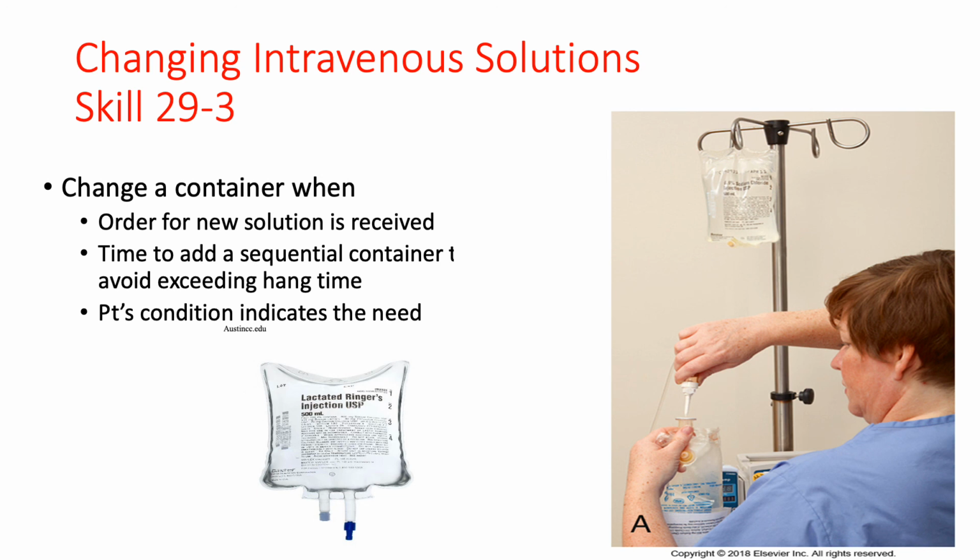If we're using a pump, typically, if it's a 1,000 milliliter bag of fluids, we wouldn't program in the entire 1,000 milliliters. We would program in maybe 950 or 975 so that the pump would alert us before it completely empties out. This is important because if the bag empties completely, the tubing might empty, and then you will end up having to prime your tubing all over again, which is going to take more time and disconnections as well.